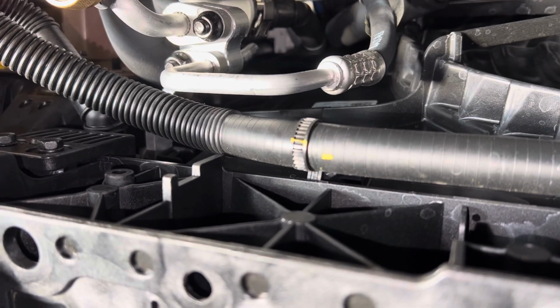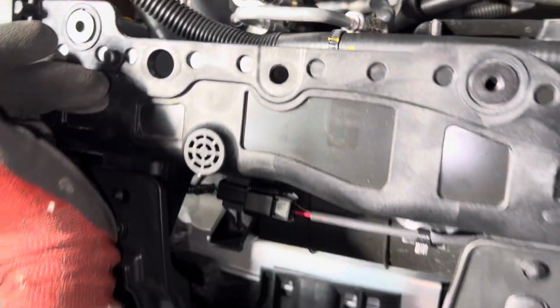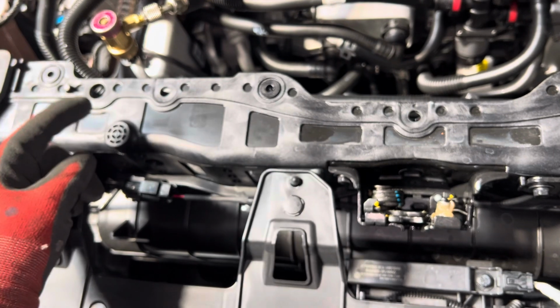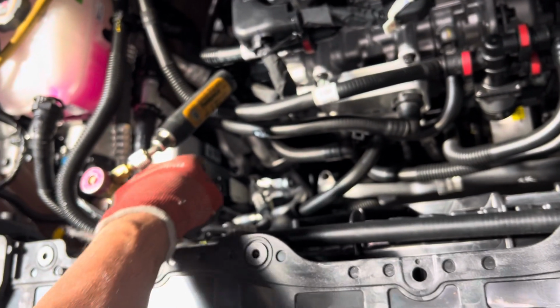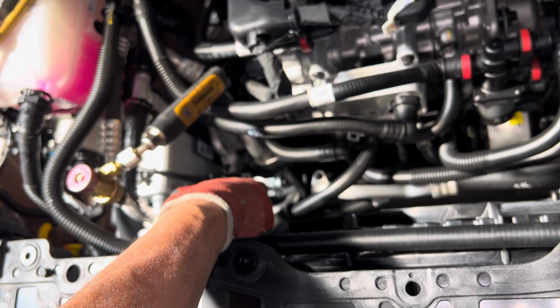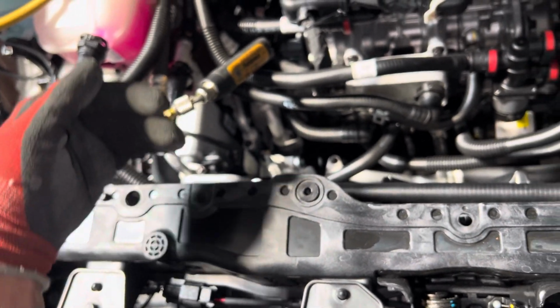I don't see the third one. Why am I missing it? Oh, okay, so this one is doing a glycol loop condenser. There is no condenser with refrigerant on this one, no main condenser. This one uses a glycol loop heat exchanger instead. It's using the plate heat exchanger with the expansion valve to chill the glycol loop and get rid of the heat from the compressor. So there's no condenser up here rejecting heat, it's all going through the glycol loop.